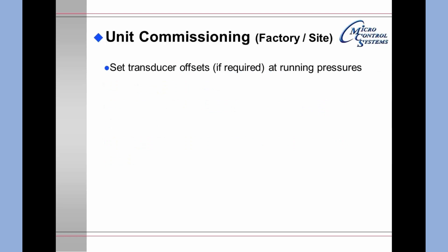You can set the transducer offsets if required, but you should do it at running pressures. That is, allow the system to get down to its operating position before testing any transducers and putting in any offsets. You should not require any offsets for amp sensors or temperature sensors. If they are not reading correctly, you need to go back and re-verify the wiring.